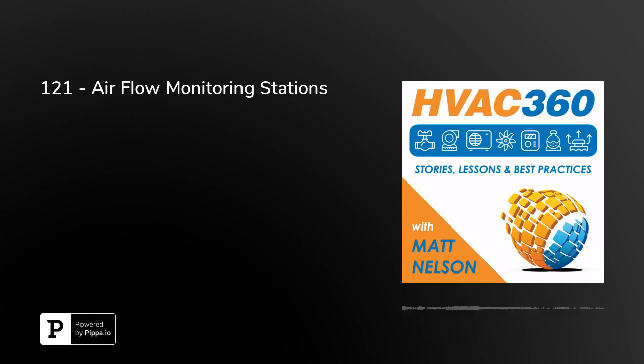Again, you have fans that are hunting. You can do hunting fans, hunting dampers. If you're using it in a control sequence and you have the outside air airflow monitoring stations updating fairly regularly, sending that off to the BAS, you could have your fans just all over the place with the control, and having hunting fans and hunting dampers constantly changing speed, constantly actuating, constantly changing. It just isn't good. Obviously, you could put an internal dampening PID in the sequence, but sometimes that's not always an available solution. So again, just be careful what you're using these airflow monitoring stations for.